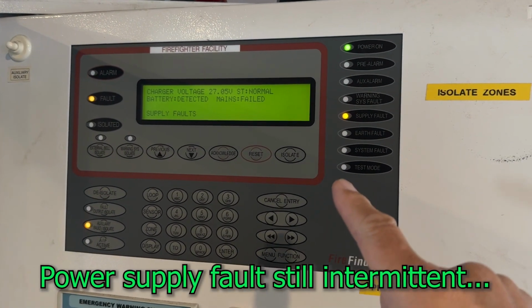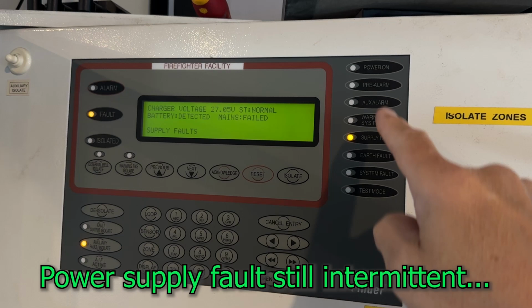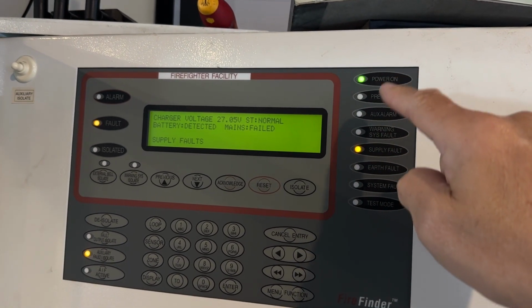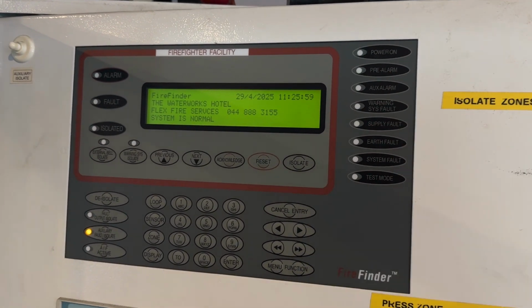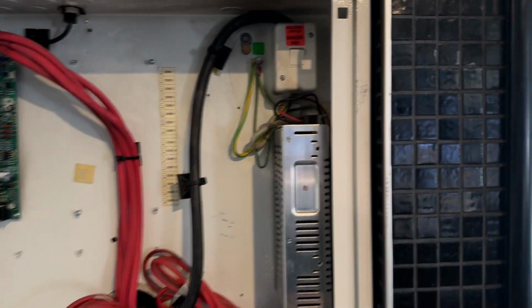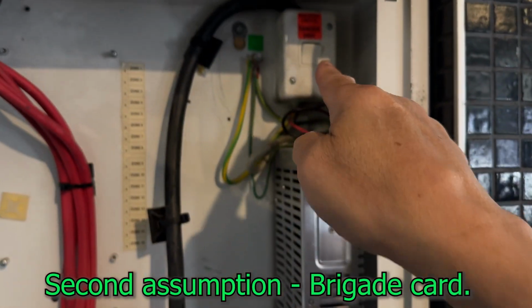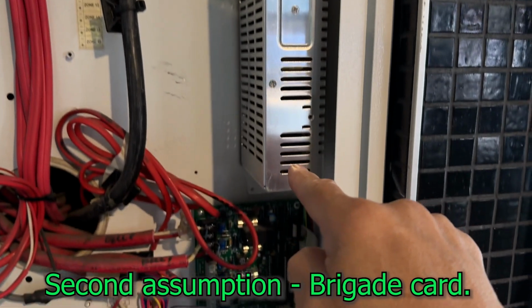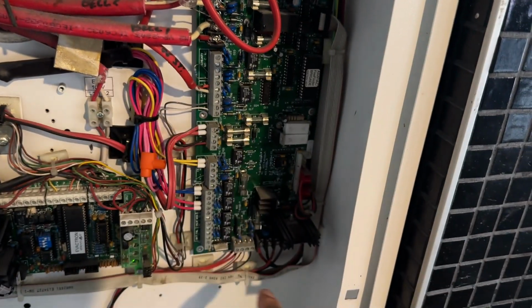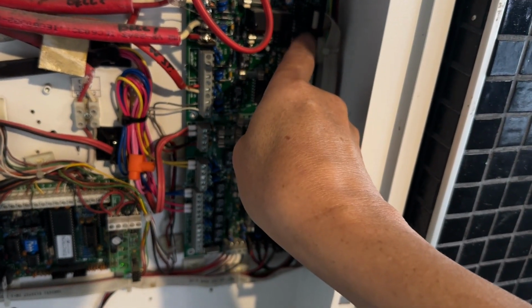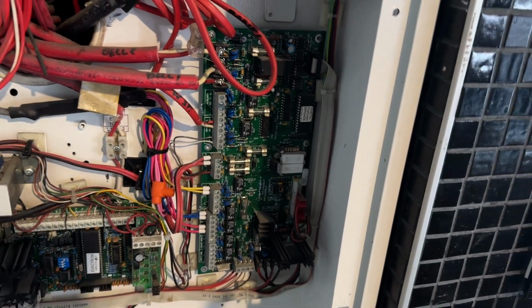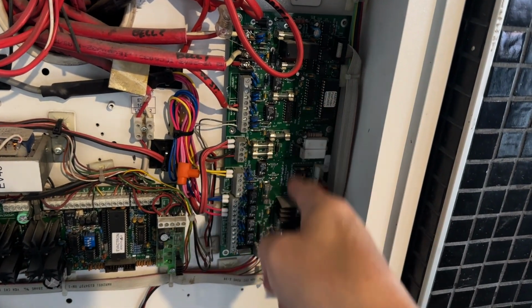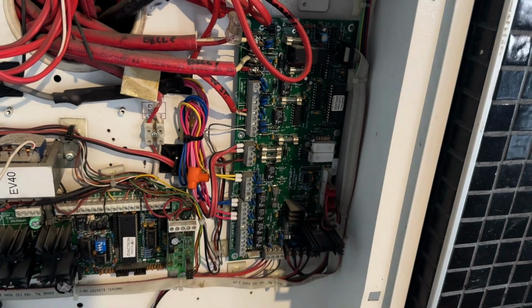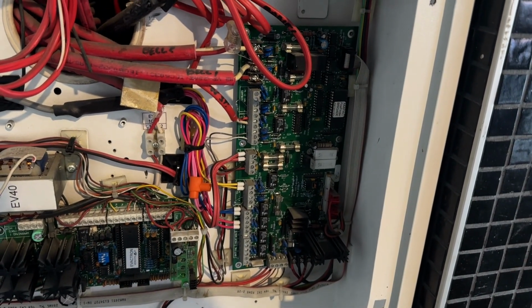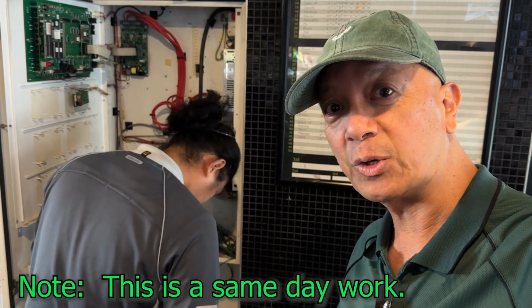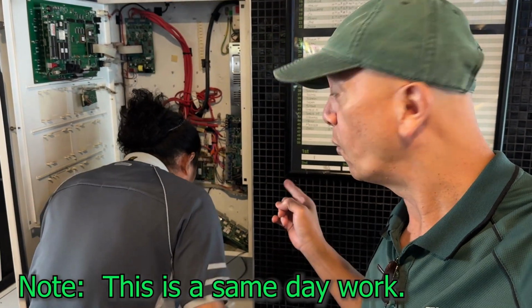So this is after we boot the system. Supply fault, mains off, and then sometimes mains on, and then supply fault, so on and off. The way I see it, we have a steady supply. That is okay. This supply looks okay. And we have a problem with this brigade card. One of those relays there is not working okay. We're going to get a relay card, a brigade card, and replace it, and let's see if we solve the problem.